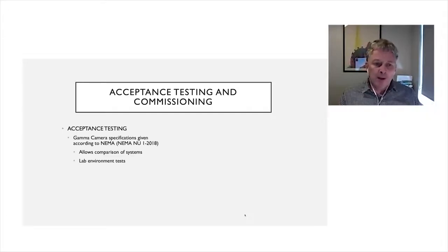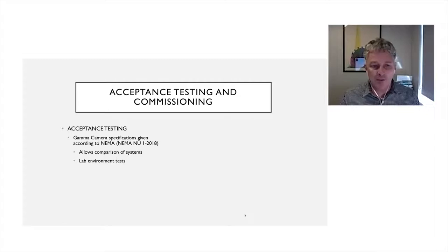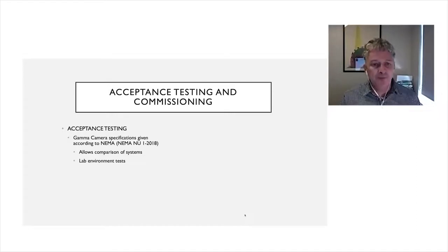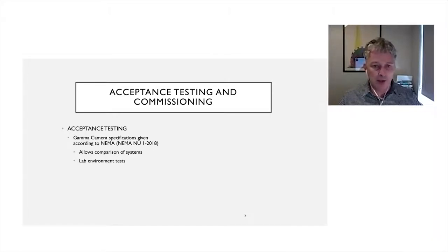In this presentation I'm focusing mostly on quality control, but it's worth briefly touching on acceptance testing and commissioning. All gamma cameras have specification sheets. Manufacturers like Siemens, GE, Mediso, or Philips will give you a list of specifications for things like spatial resolution or energy resolution. These are generally defined by the body called NEMA — a North American body used internationally. For gamma cameras, these specifications are listed in document NEMA NU 1-2018.